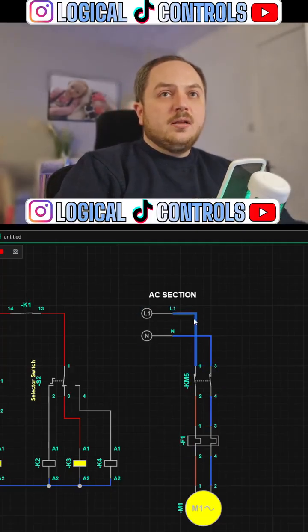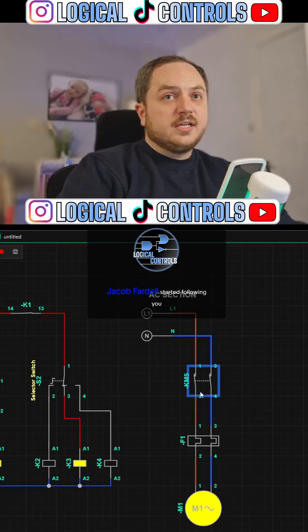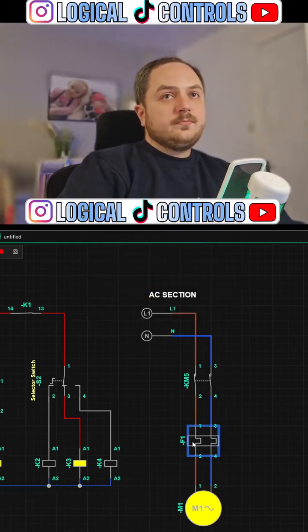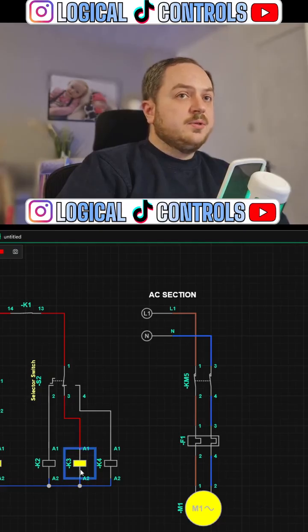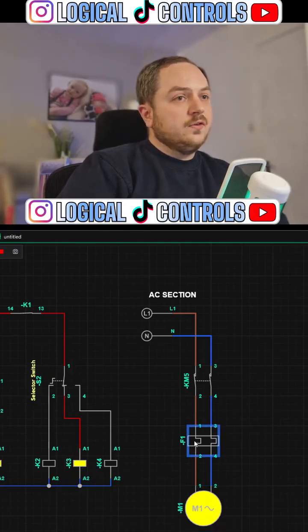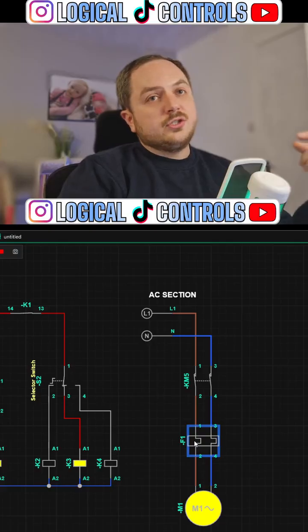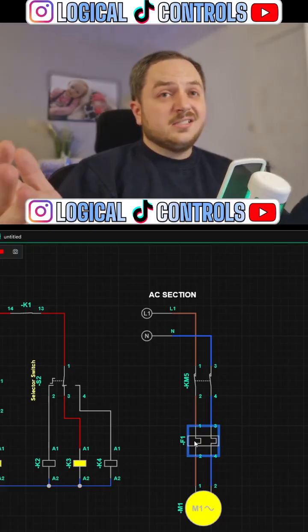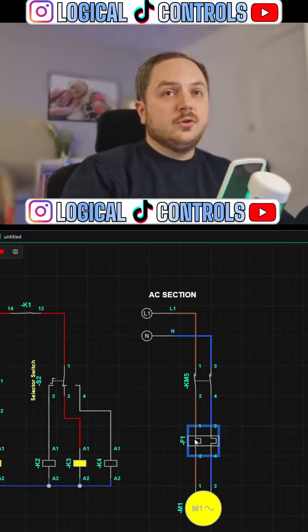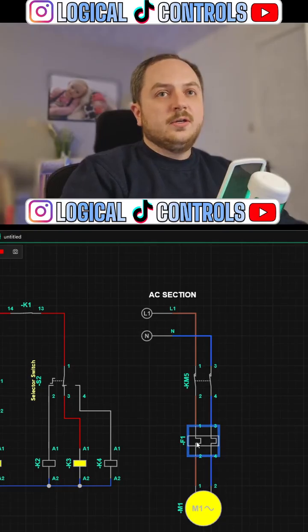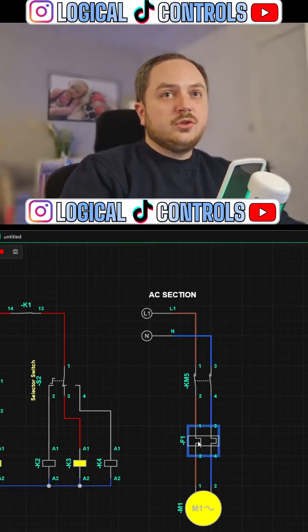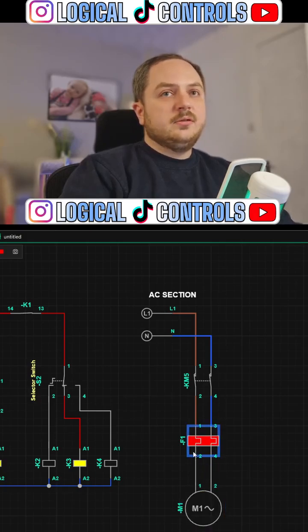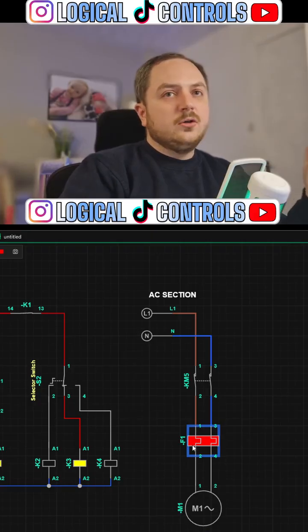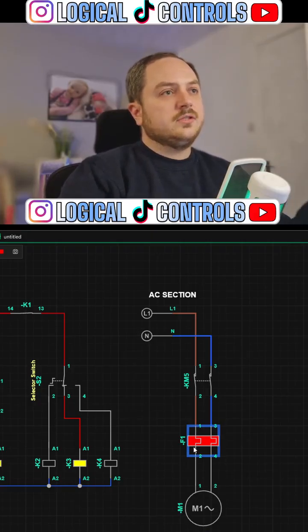Yeah, so live, neutral, both going through the contactor contacts. There's also an overload. The only way, with this switch being in this position, of this motor ever stopping is if the overload was to trip. And the overload might trip because, as it's called, it's overloaded. You've put too much load on the motor. It's a thermal overload. If the motor pulls too much current for a length of time, the overload's going to trip. I click that button, the motor trips, and then you would have to go and reset that. You can get auto resets on thermal overloads, so once they've cooled down, because they're like a bimetallic strip.